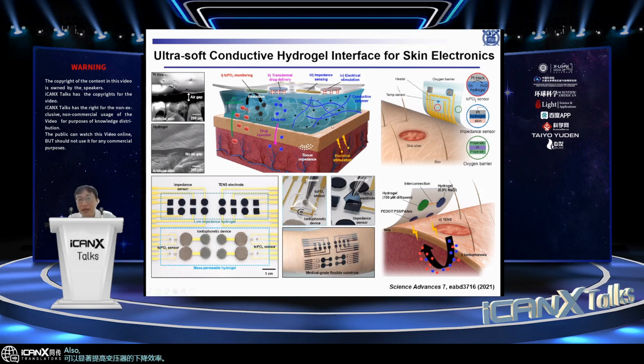Also, by adding conducting filler like PEDOT:PSS conducting polymer, the ultra-thin hydrogel layer can have high conductivity and low impedance, and therefore the sensing quality of the impedance sensor and the stimulation efficacy of the electrical stimulator can be improved significantly. So by simply adding a very thin, ultra-thin conductive hydrogel layer, all the sensing and the feedback therapy quality can be significantly improved.